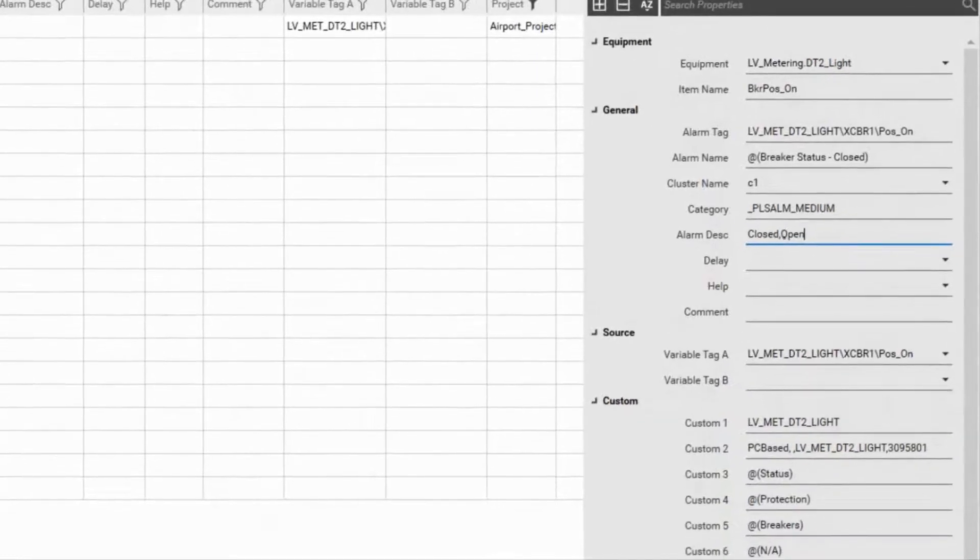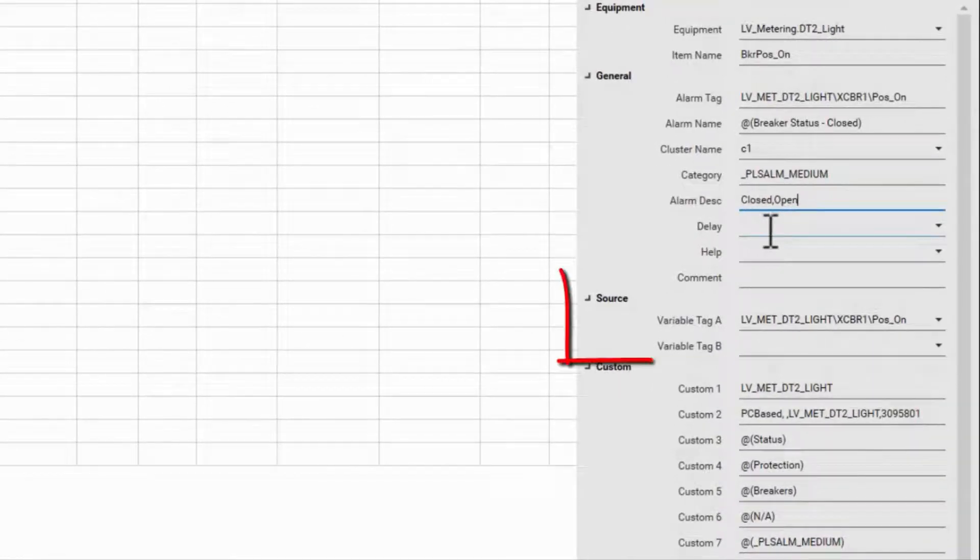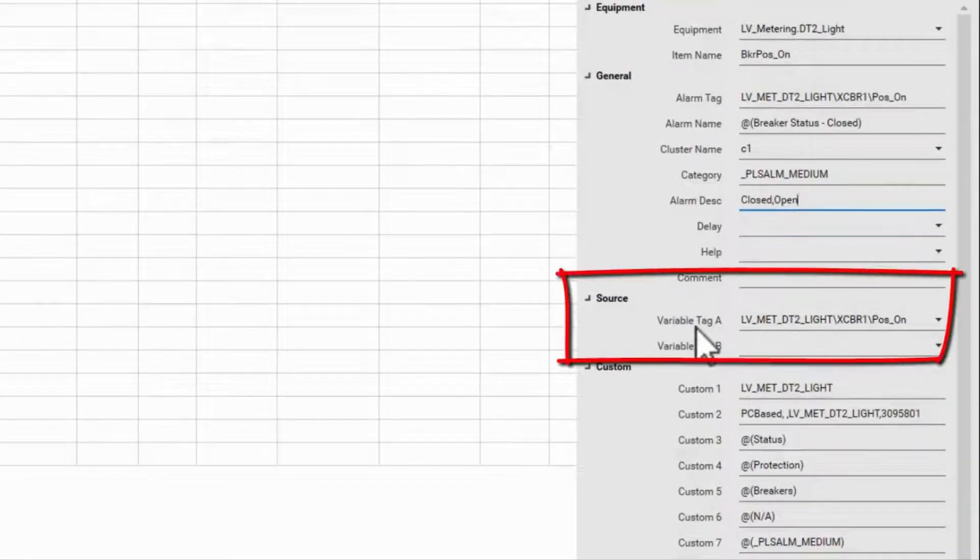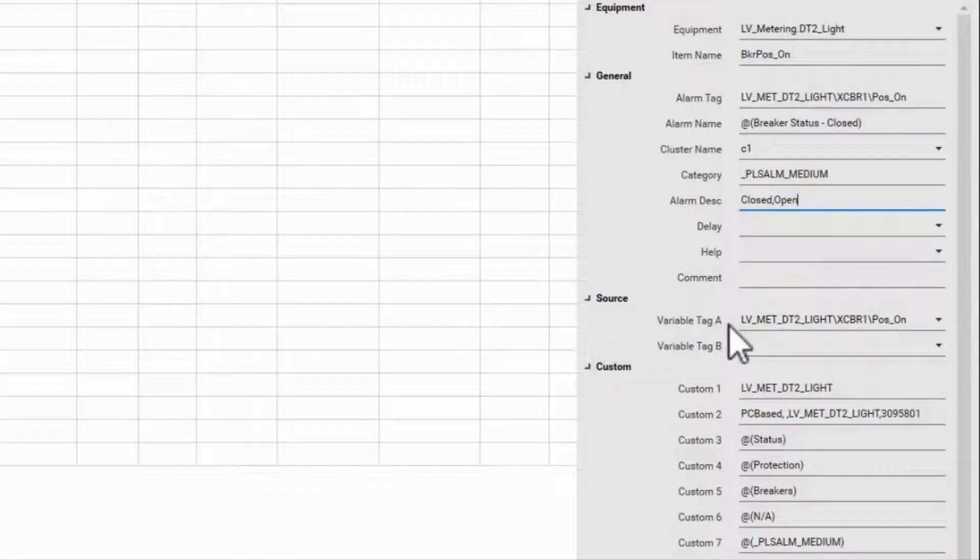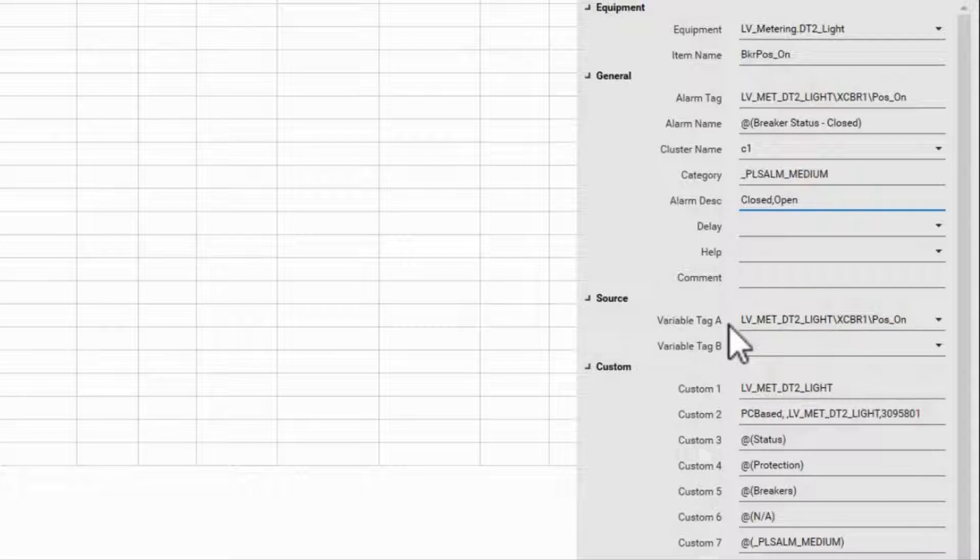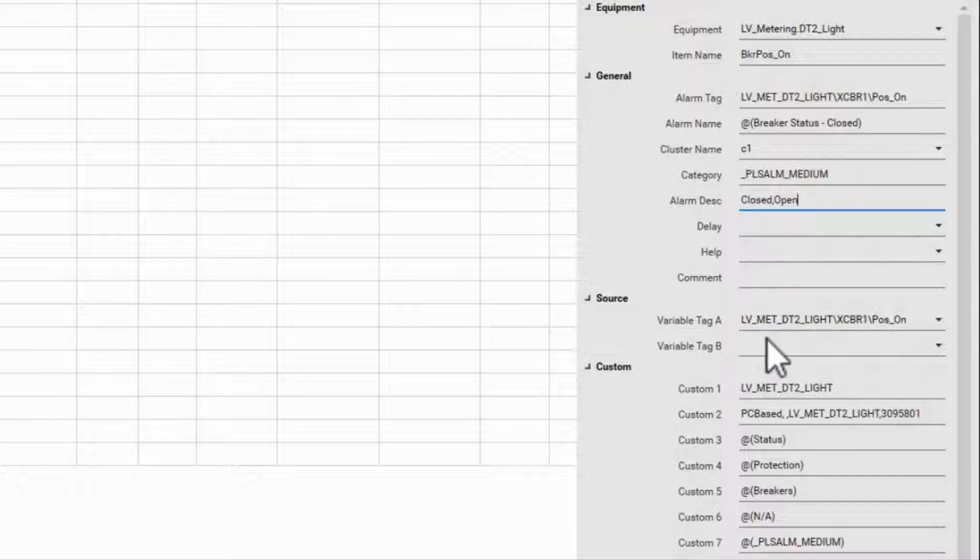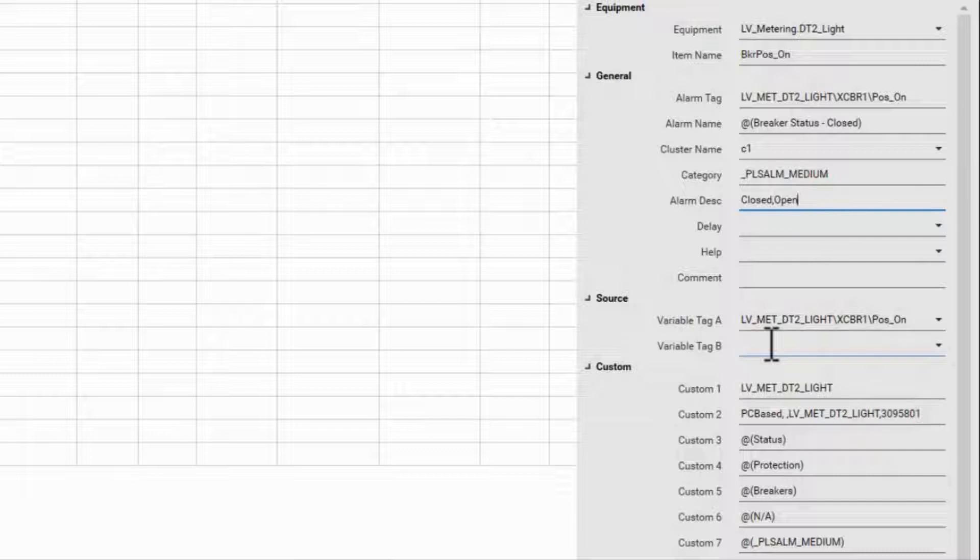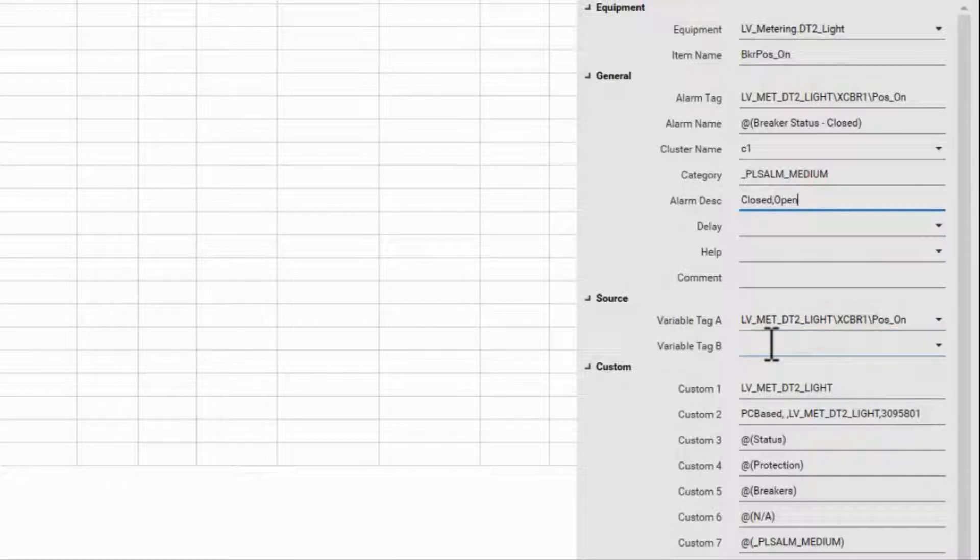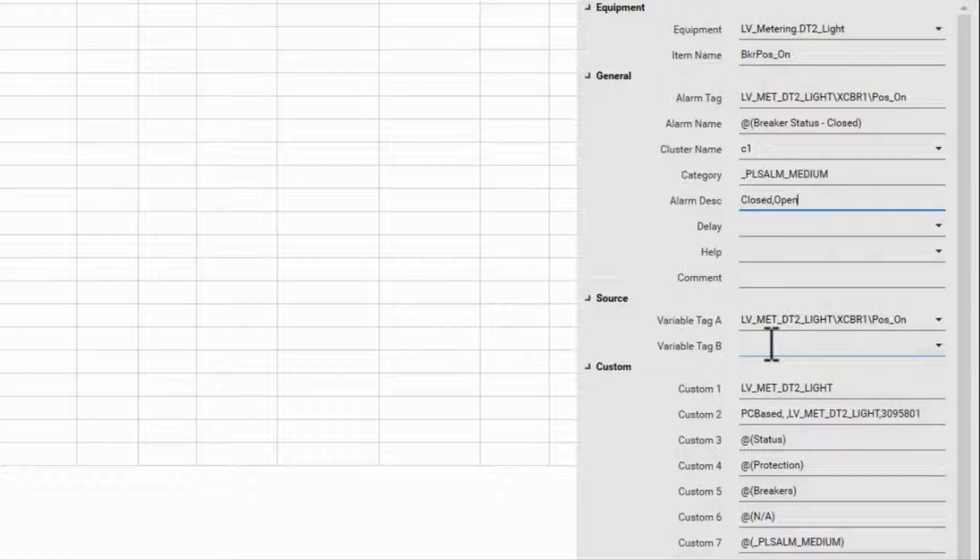What I want to show you is the source section. Here we have two variable tags. Normally, only one of these is filled in by profile editor, the variable tag that we want to trigger the alarm. We can also add a second tag to perform a logical AND between the two. That is, the alarm will only trigger when both tags are active.